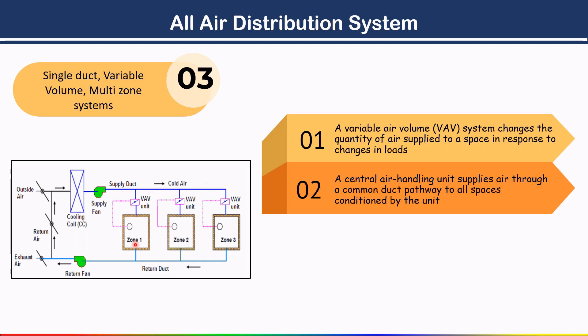When the number of people decreases, the temperature level also reduces. We know that for human comfort we must maintain 22 degrees Celsius. In each room a thermostat is installed. That thermostat sends the temperature level and signals the VAV box that this zone requires a lower air flow rate. In this way the system works.